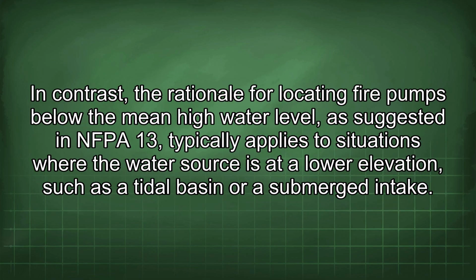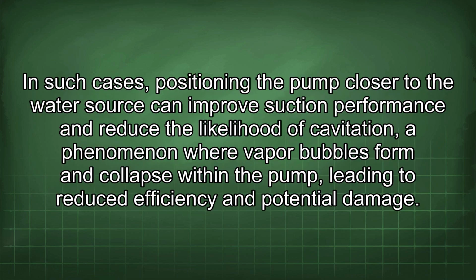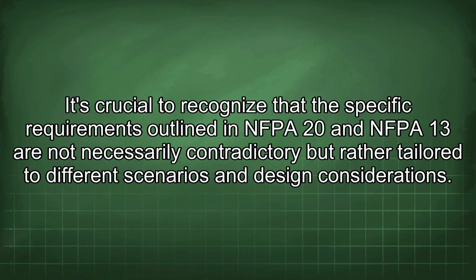In contrast, the rationale for locating fire pumps below the mean high water level, as suggested in NFPA 13, typically applies to situations where the water source is at a lower elevation, such as a tidal basin or submerged intake. In such cases, positioning the pump closer to the water source can improve suction performance and reduce the likelihood of cavitation, a phenomenon where vapor bubbles form and collapse within the pump, leading to reduced efficiency and potential damage. It's crucial to recognize that the specific requirements outlined in NFPA 20 and NFPA 13 are not necessarily contradictory, but rather tailored to different scenarios and design considerations.